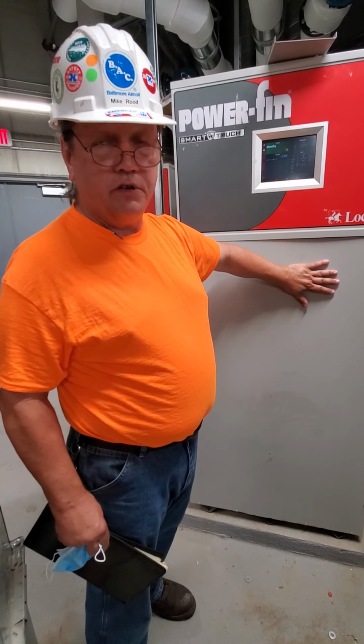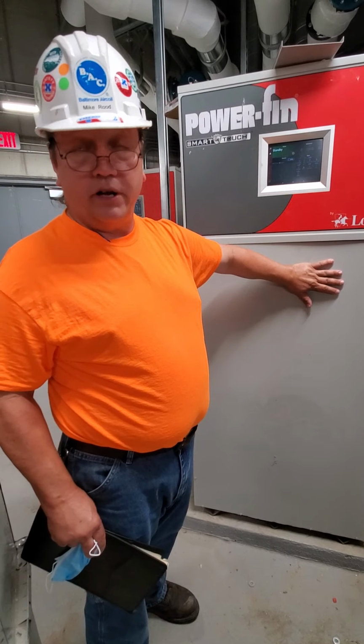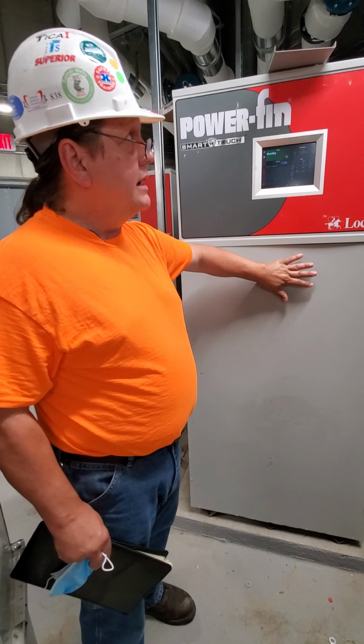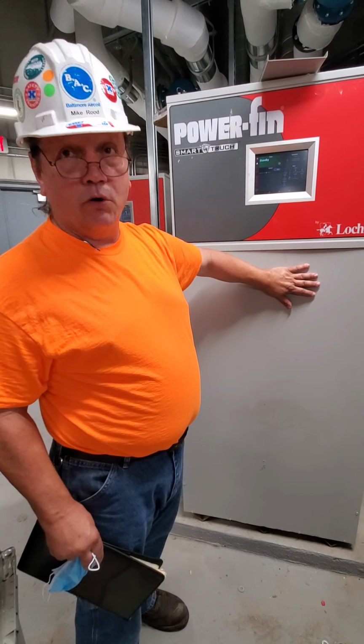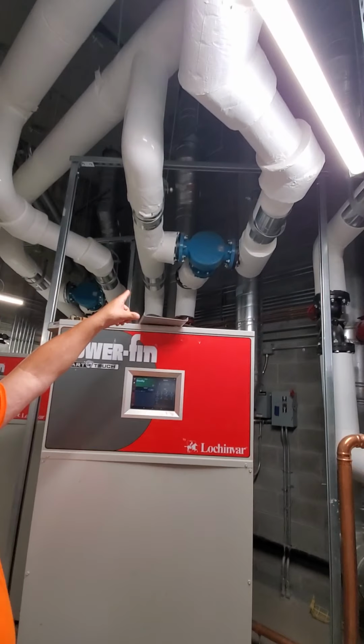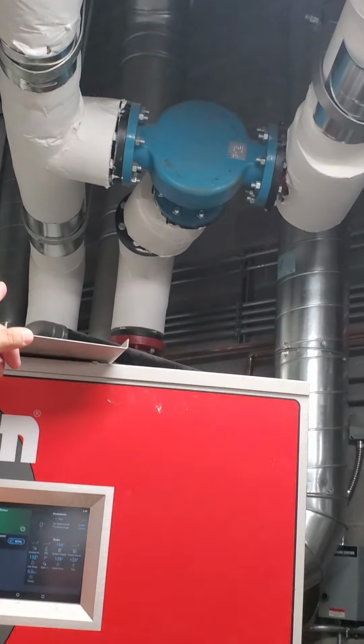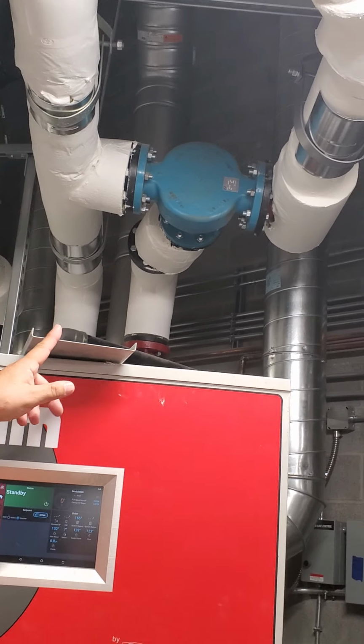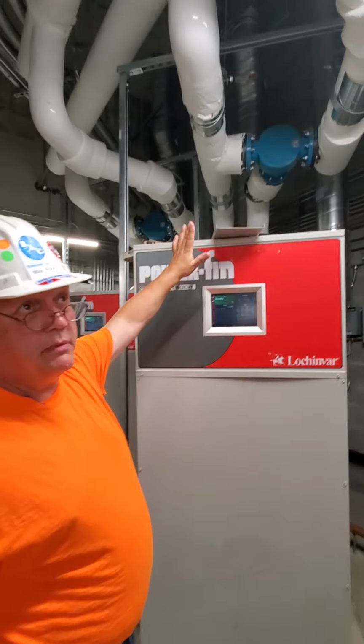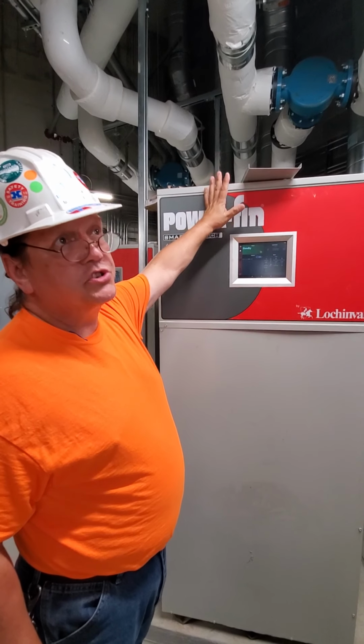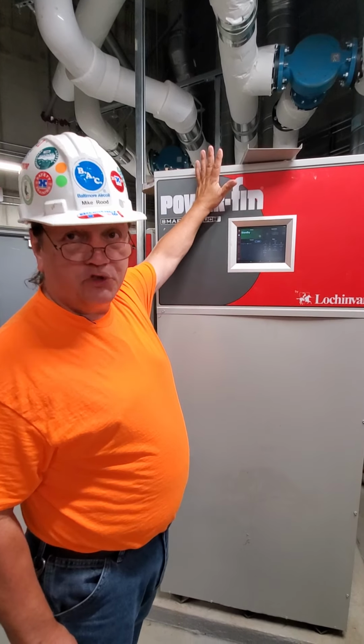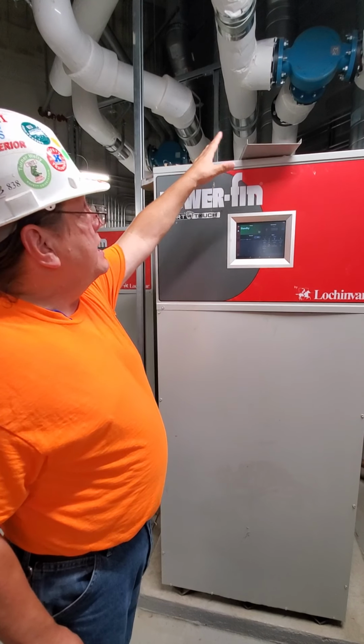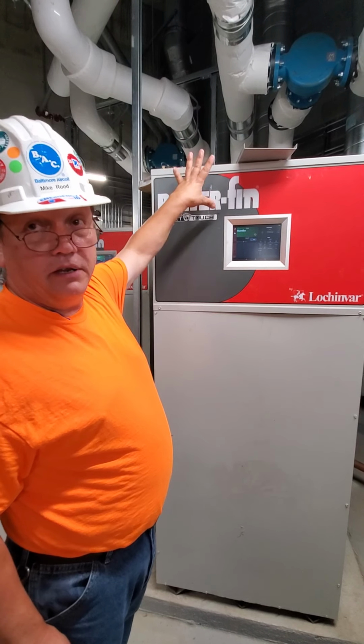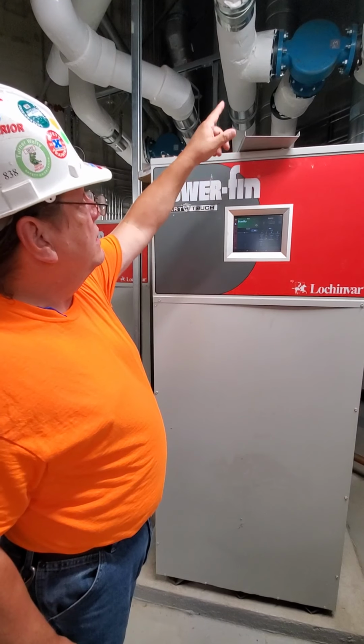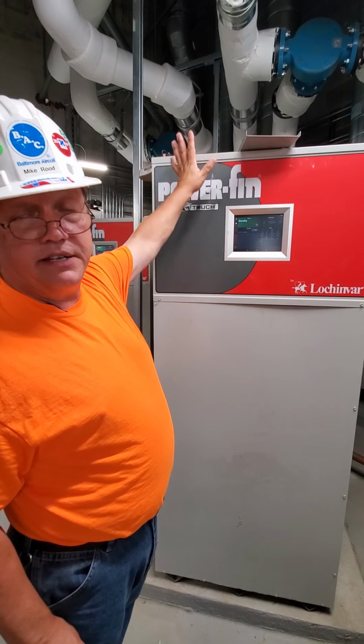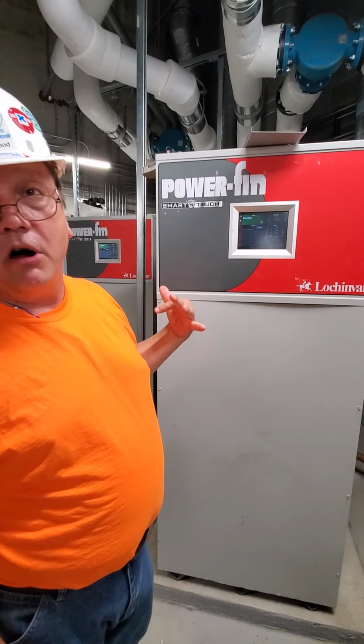So the minimum water temperature of this boiler is 140 degree inlet temperature. If it's getting any colder than that, then there's a 3-way valve up here that's probably malfunctioning. On a cold startup, if the entire system's cold, you may see that cold startup for probably about 2 minutes. And at that time, once the loop gets hot within the boiler loop right here, that valve starts to open and it'll maintain 140-degree inlet coming to the boiler automatically.